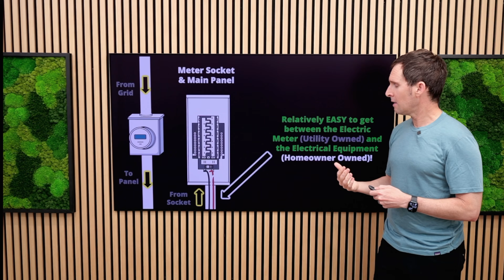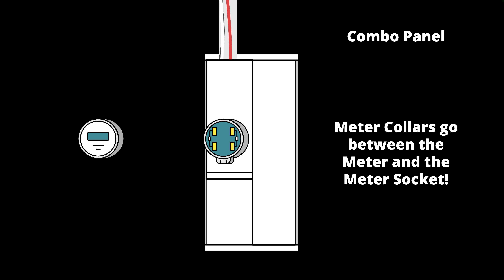If we can't get between here, if we can't find a spot, what the meter collar does is sit behind the meter and create a new point of connection, or point of intercept, between the power from the utility and the homeowner's electrical system. This meter collar makes an enormous difference for a variety of reasons, which we'll dive into next, but now you understand why and how this meter collar is installed.